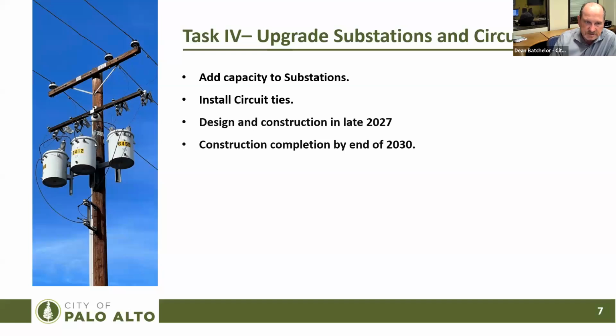We're also installing circuit ties. The way the system was built, they have what we call feeder lines - the main lines that run from the substations all the way out to the end of a run that might have about 2,000 homes on it. If there's an outage - could be a tree in the line, could be a bad piece of equipment - sometimes that will relay all the way back to the substation, and it shuts the whole entire feeder down.